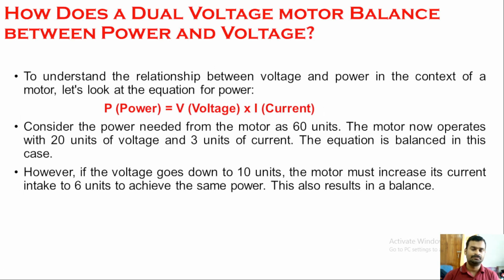So how does this power balance take place in the motor? It is very simple to understand. Take 60 units of power, of which 20 units of voltage and 3 units of current contribute to the 60 units of power, and if you increase or decrease any one of these parameters, you can balance the power. So if the voltage is increased, the current will be decreased. Vice versa, if the voltage is decreased, then the current will be increased. So the power will be maintained constant anyhow. That is how the power balance takes place in the dual voltage motor.